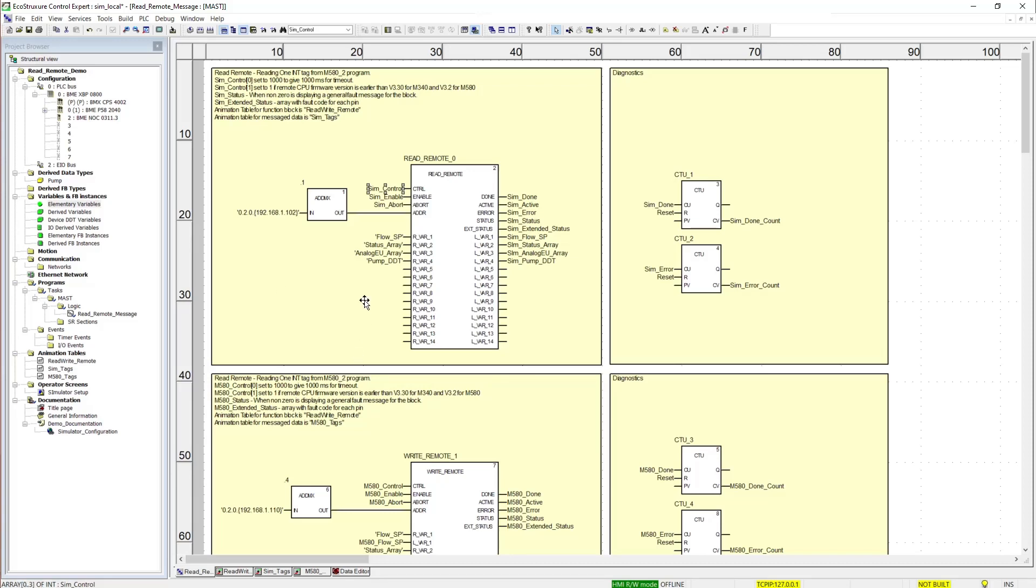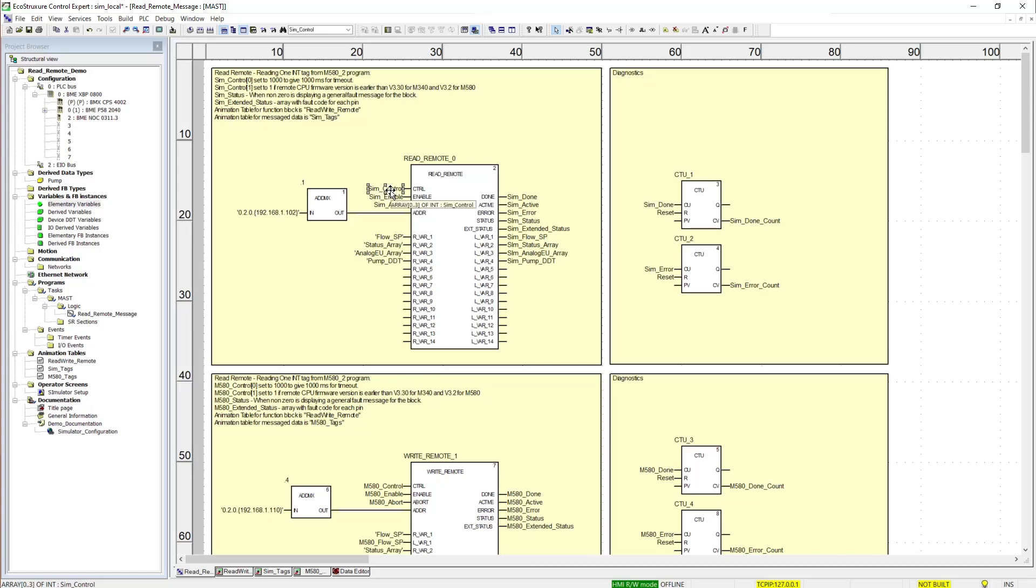The first integer in that array is the timeout setting. And then the second integer in that array is the firmware designation for the PLC we are talking to. So if you're talking to an M340 that is less than version 3.3 or an M580 that has a firmware revision less than 3.2 we need to put a 1 in that integer of that array.